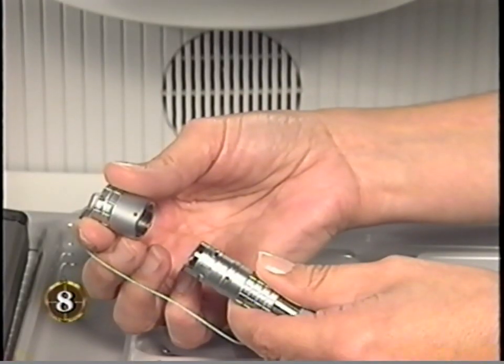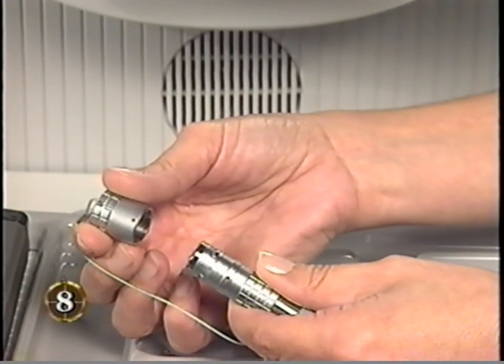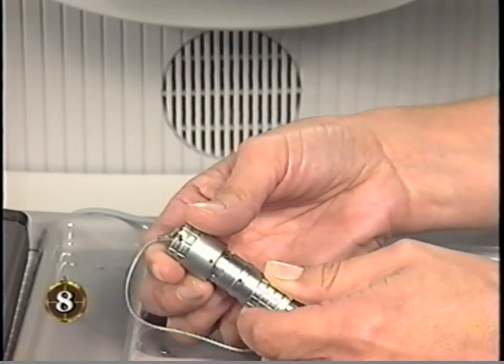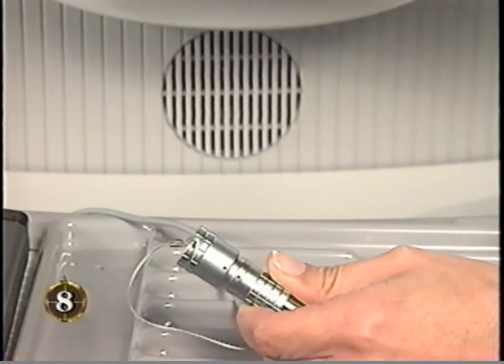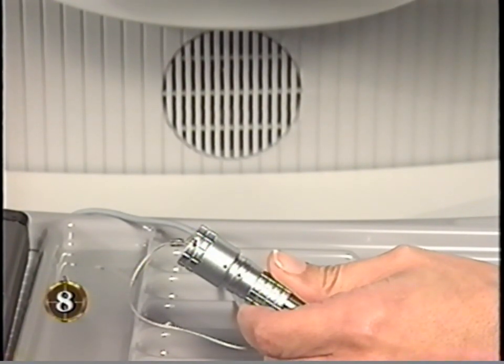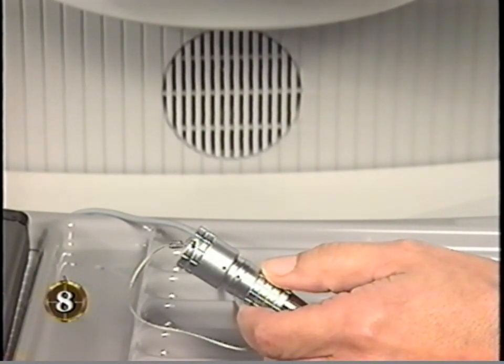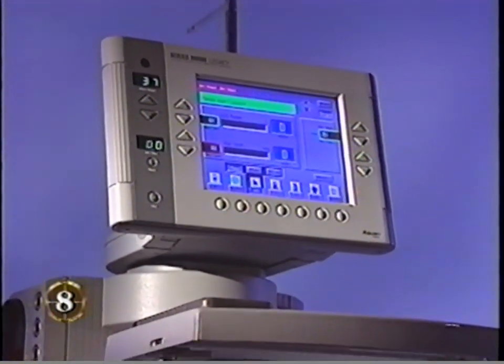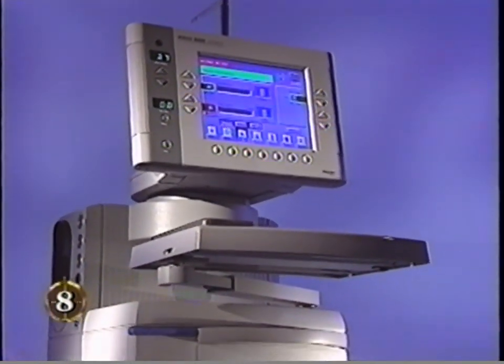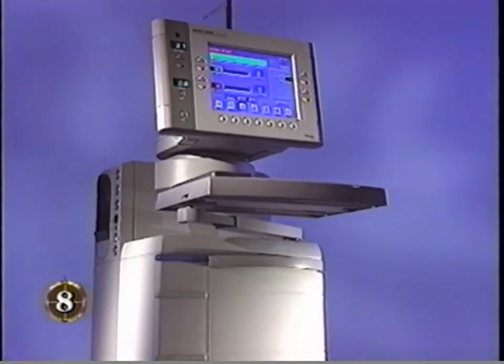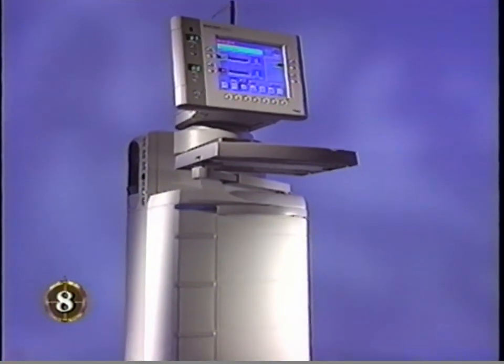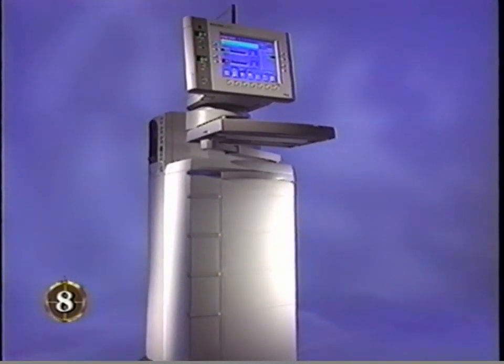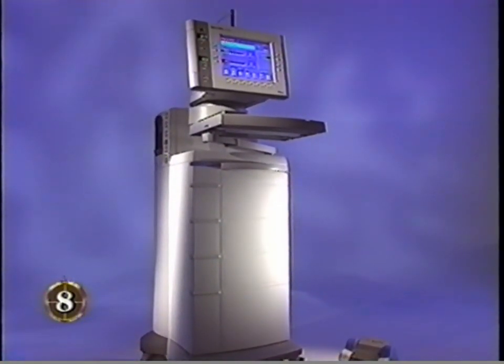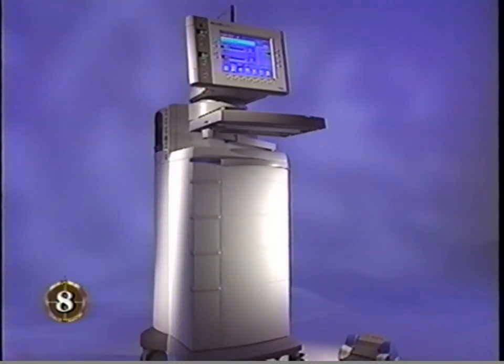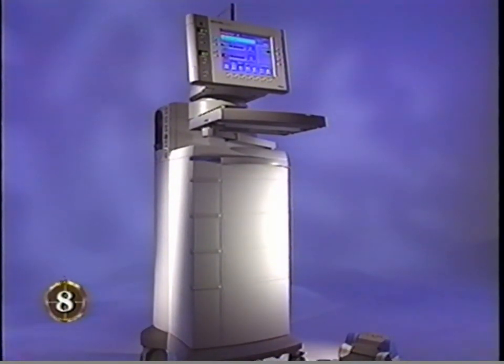Before sterilizing the ultrasound and hydrosonics handpieces, always secure the connector end cap. Then place the handpiece in the sterilization tray to prevent damage during handling and autoclaving. To maximize the life and performance of reusable handpieces, allow them to air cool for about 15 minutes following steam or flash autoclaving. Consult the operator's manual for Alcon's suggested sterilization times and temperatures, or reference current AORN standards or the hospital standard procedures for current specifications.